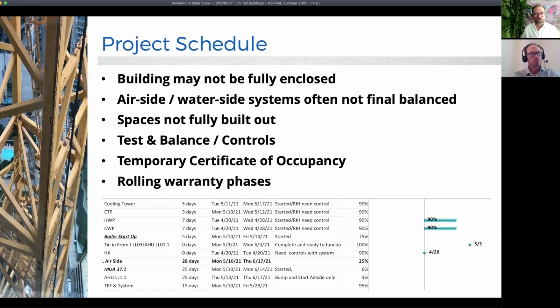One thing we run into a lot also is the spaces not being fully built out. So commercial office buildings are a great example. How do you test and balance something that was built as a core and shell, but doesn't have the occupants? So it's not been built out with terminal units in the space. And so one of the solutions there that we've done in a lot of our projects is have the ductwork be open on some floors to be able to test the air handling equipment.